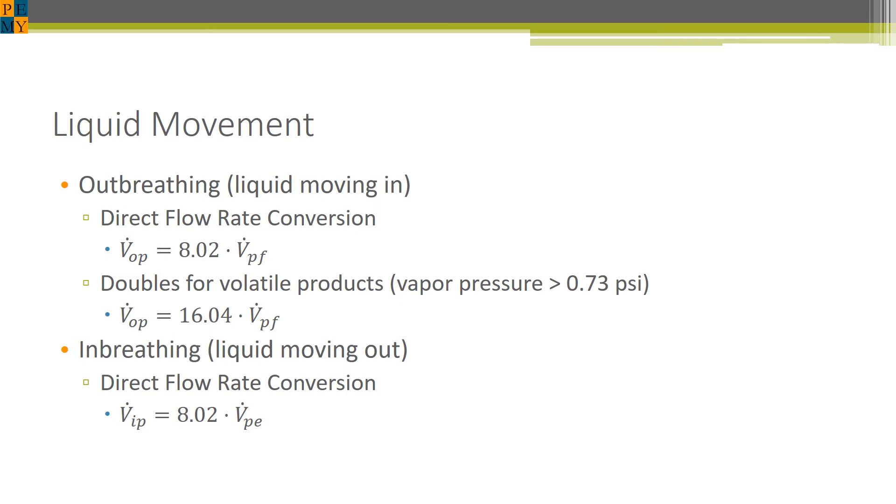However, for volatile products, which are defined as products with a vapor pressure greater than 0.73 PSI, this can actually generate an additional amount of vapors. So this flow rate is actually doubled. However, it is still just a straight flow rate conversion. For inbreathing, this does not happen. When liquid is getting pumped out of the tank, there's not that extra vapor generation inside the tank. So once again, it's just a one-to-one ratio with that 8.02 unit conversion factor.